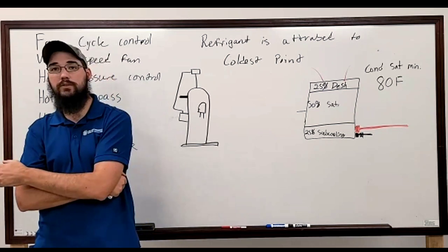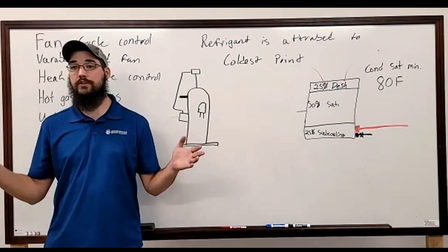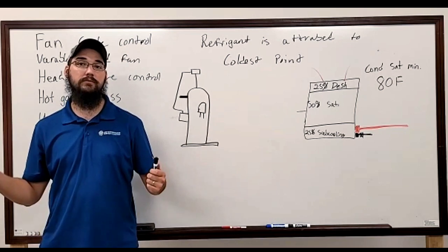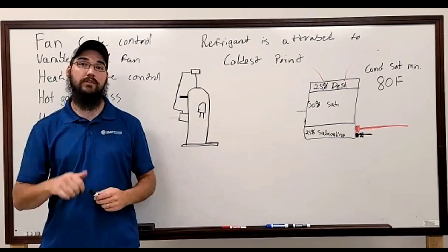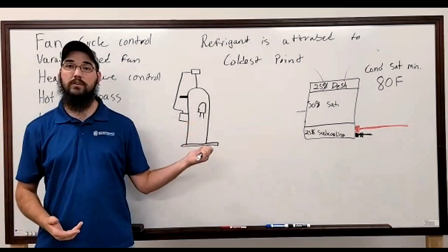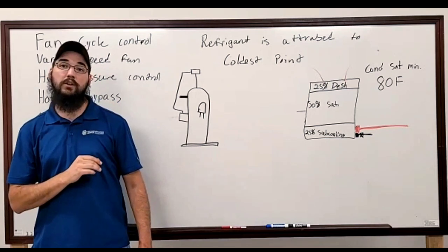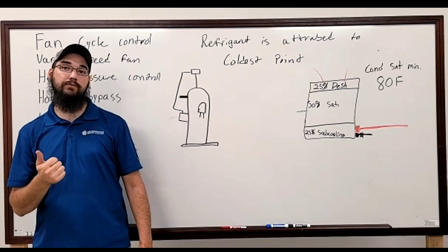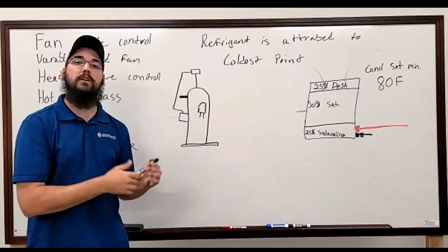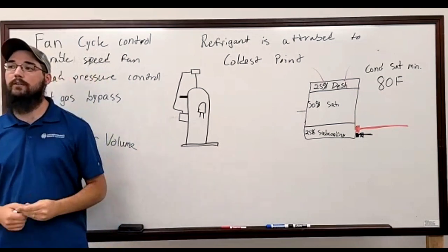Increases efficiency and life cycles tremendously because on a motor, how are motors rated in America or in general? When a motor is designed and built, how is it rated for life cycle? Is it hours? It's starts, stops, specifically starts. When they build and design a motor, they design it based on the starts. If we can reduce the number of starts, you're extending its life. And we require a fraction of the energy because we're not at locked rotor. So instead of, you know, trying to go harder, right, this is where unloading control becomes a really big factor. But it plays into our capacity control because we are taking load off of the system.